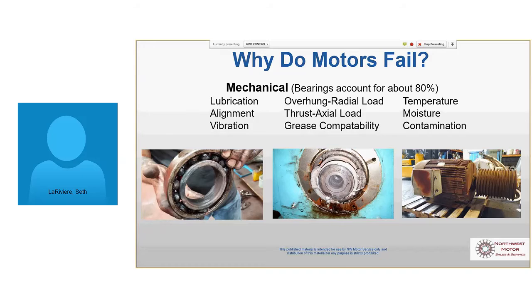There are a lot of different philosophies in the industry about maintenance schedules on motors. Should you re-grease a motor? Should you not re-grease? Should you just let it run to failure? There's a lot of people that have actually decided that their motors run longer if they never let their maintenance guys lube them. They just run to failure. I wouldn't recommend that on a really large, expensive motor, but on something of this size, that's totally understandable. That motor will run at least 7 years without ever being greased.